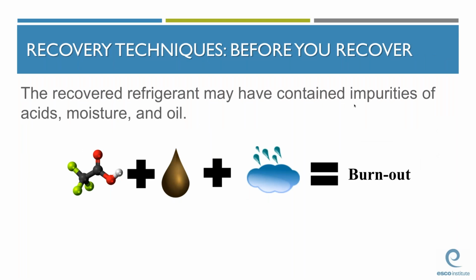Always alert your students that recovered refrigerant may contain impurities such as acids, moisture, and oil. So instruct your students that if they smell a sharp, pungent odor while gauging up on a system in preparation to recover refrigerant, they should alert you immediately. Sharp, pungent odors are an indication that a compressor burnout has occurred. If the system has indeed experienced a compressor burnout, an oil sample should be taken so that it can be tested for the presence of acid.